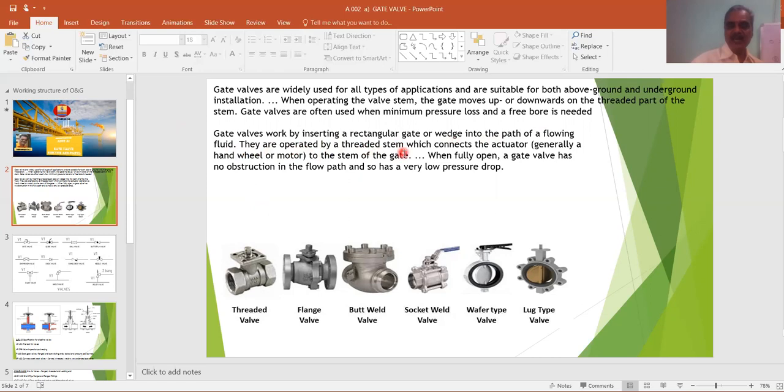Gate valve works by inserting a rectangular gate or wedge into the path of a flowing fluid. They are operated by a threaded stem. The stem connects the actuator, generally a hand wheel or motor, to the stem of the gate. When fully open, a gate valve has no obstruction in the flow path and so has a very low pressure drop.